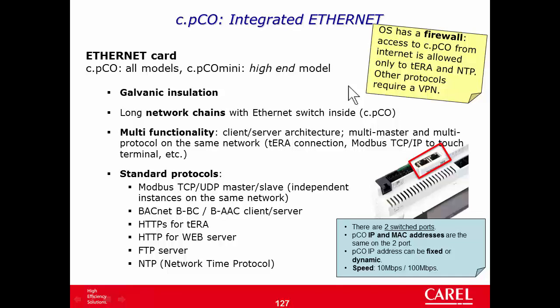The only way to pass through the firewall is to implement a VPN, because with a VPN the c.pCO and the other device — PC or another controller — will belong to the same network. Only Tera protocol (HTTP for Tera) and NTP are not behind the firewall, so you can connect c.pCO to the Tera service without configuring any VPN.